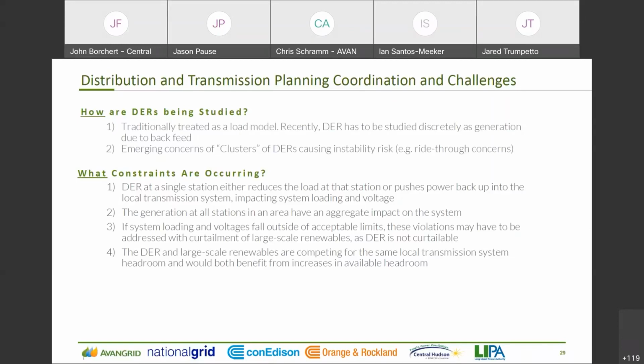Besides this potential stability risk, what are some constraints found in the transmission due to DER? DER backfeeding can result in thermal overloads but can also cause high and low voltages. This is more prevalent when looking at the aggregate of DER at multiple stations within a small load area — small relative to the transmission, that is.